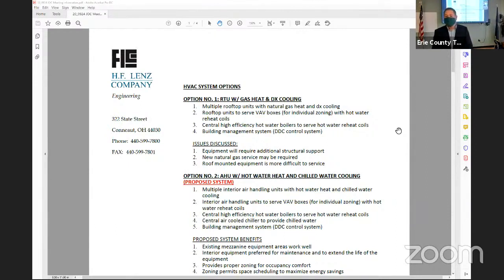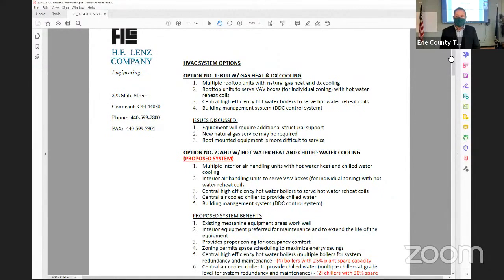The second thing we wanted to accomplish was talking about the HVAC system. At the last meeting, we had a couple of tasks on our end to complete and provide some additional information. As a refresher, the two options we were looking at: the first option being rooftop units, gas fired with DX cooling, serving VAV boxes for the individual zones throughout, with the VAV boxes having hot water reheat coils and small hot water boilers to accommodate.